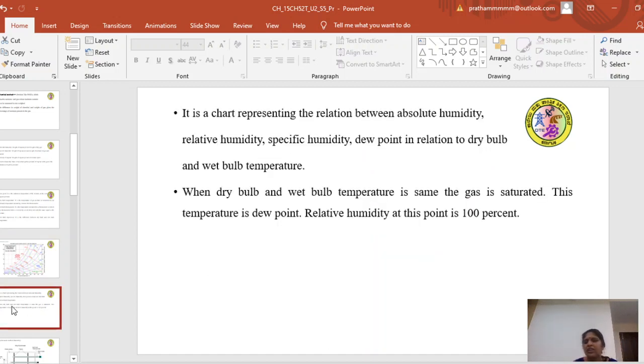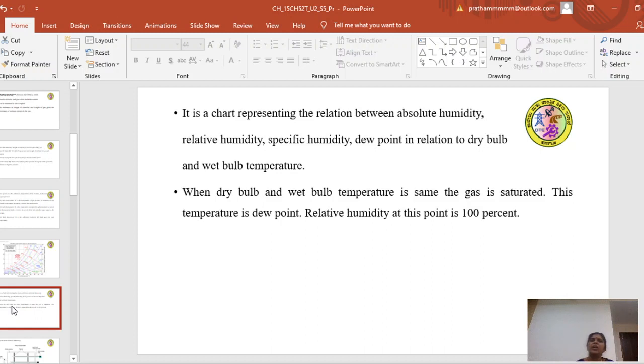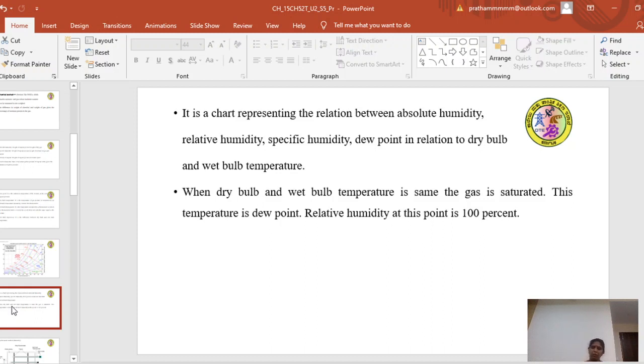The psychrometric chart represents the relationship between absolute humidity, relative humidity, specific humidity, and dew point in relation to dry bulb and wet bulb temperature. When dry bulb and wet bulb temperature are the same, the gas is said to be saturated and it cannot absorb any more moisture. This temperature is the dew point, at which the relative humidity is 100%.